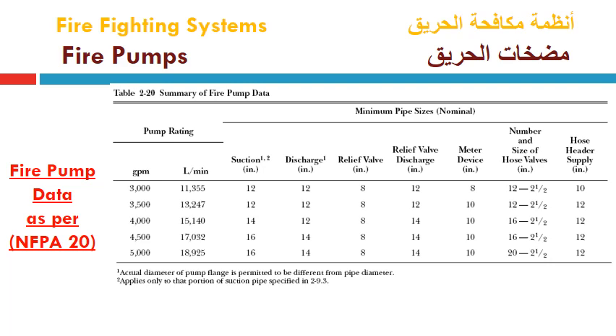So if we have a pump with 3000 GPM, we must use a suction line not less than 12 inch, and also the discharge line. However, the relief valve should be 8 inch. The relief valve discharge line should be the same size as the discharge line, 12 inch, and the metering device should not be less than 8 inch. Twelve hose valves of 2.5 inch each should be used and connected on a hose header supply not less than 10 inch in diameter.